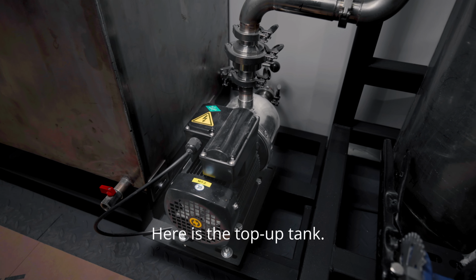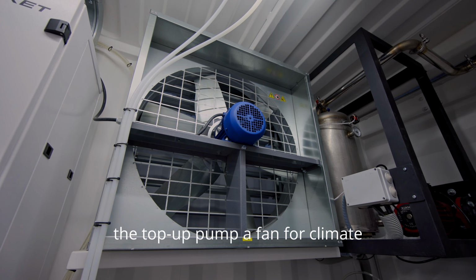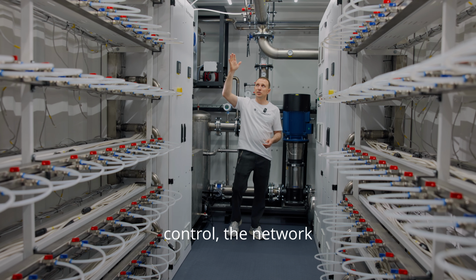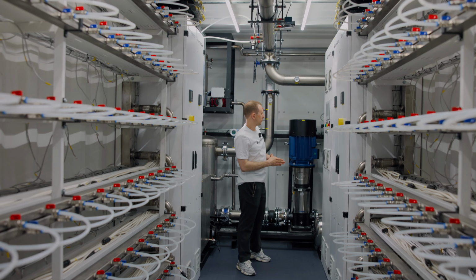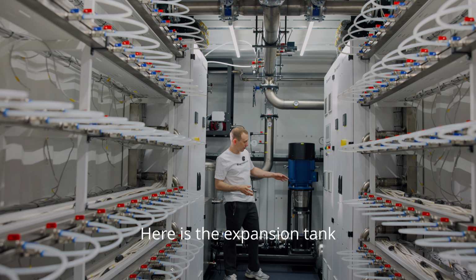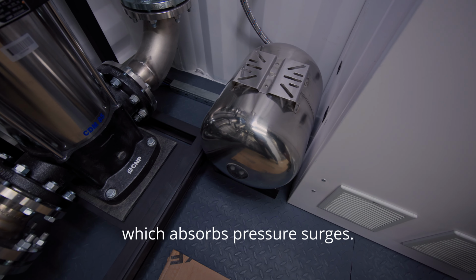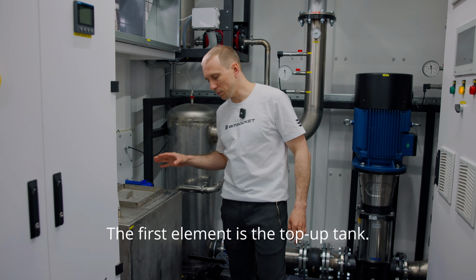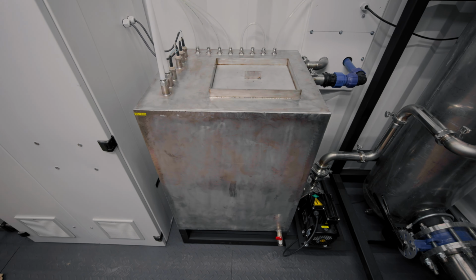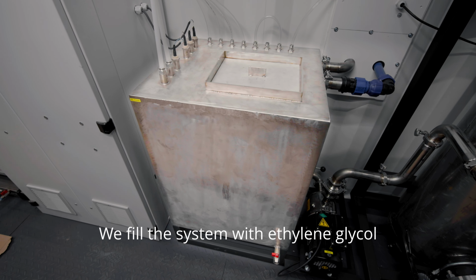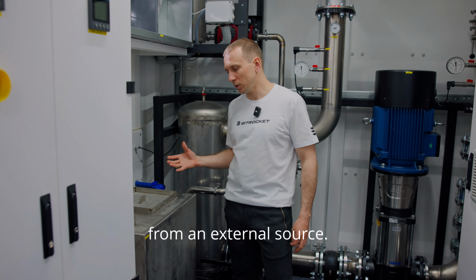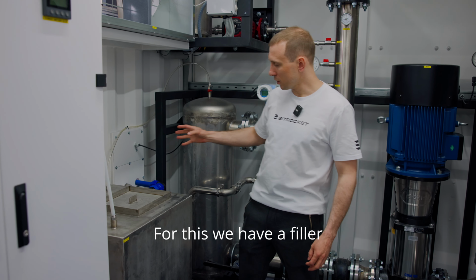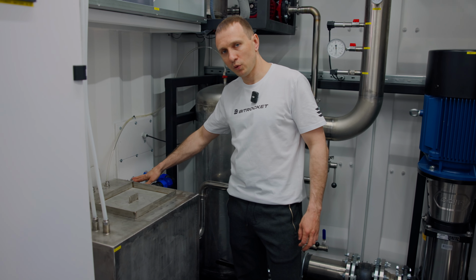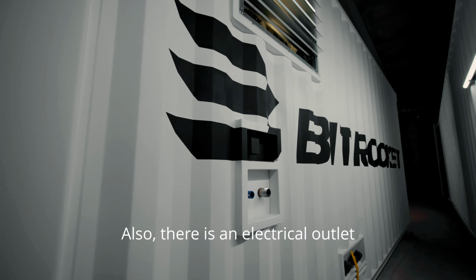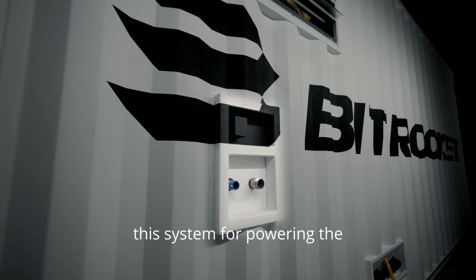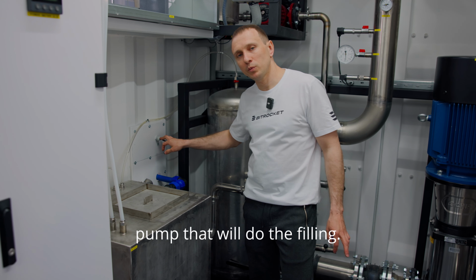Here is the top-up tank, the top-up pump, a fan for climate control, the network system, which we will discuss separately. Here is the expansion tank, which absorbs pressure surges. The first element is the top-up tank. Here's how it works. We fill the system with ethylene glycol from an external source. For this, we have a filler neck outside the container. Also, there is an electrical outlet outside controlled by the system for powering the pump that will do the filling.